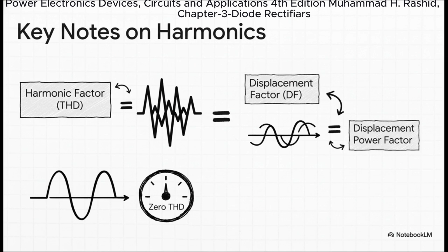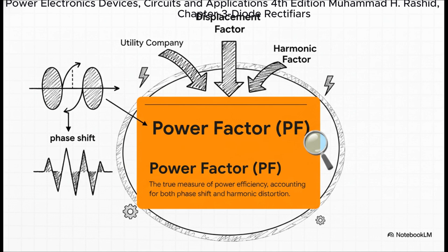You'll also hear displacement factor called displacement power factor, or DPF. And that brings us to the big one, the true power factor, PF. This is the metric that tells the whole story, combining both the timing issue, our displacement factor, and the waveform shape issue, our harmonic factor, into one single number. This is the number that really matters at the end of the day, the one the utility companies are looking at.